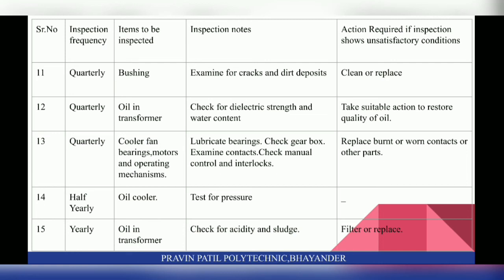On a quarterly basis, check bushings — examine for cracks and dirt deposits; clean or replace if necessary. Check oil in the transformer for dielectric strength and water content; take suitable action to restore oil quality. Also check cooler fan bearings, motors and operating mechanism: lubricate bearings, check the gearbox, examine contacts, check manual control and interlocks. Replace burnt or worn contacts or other parts as required.